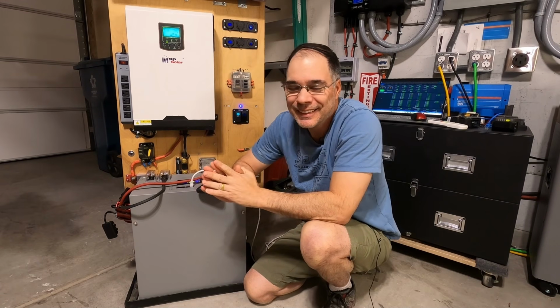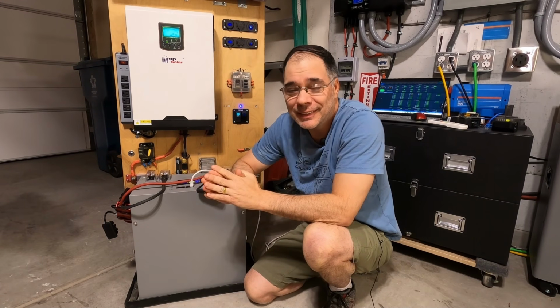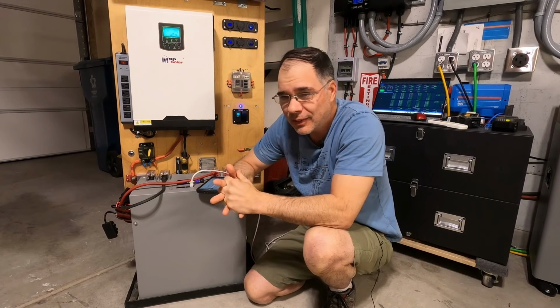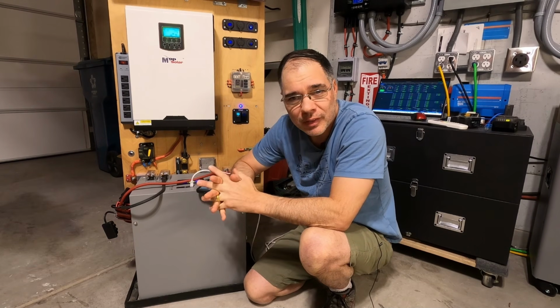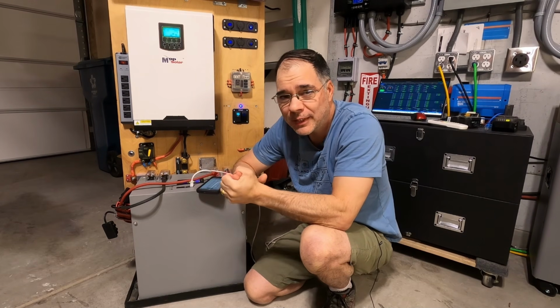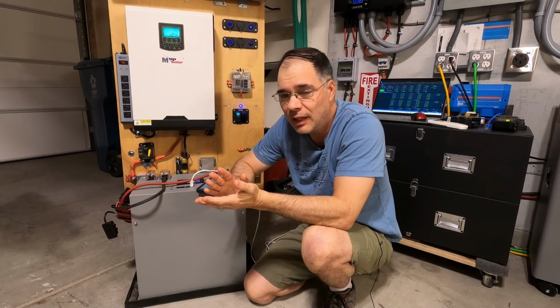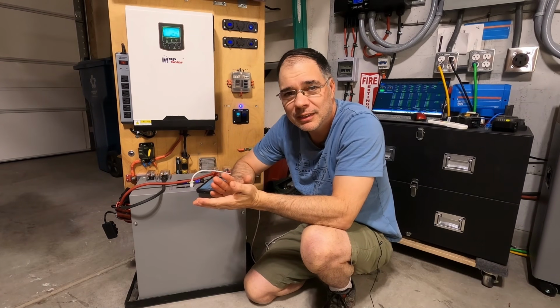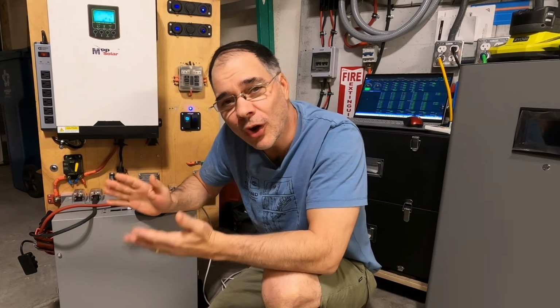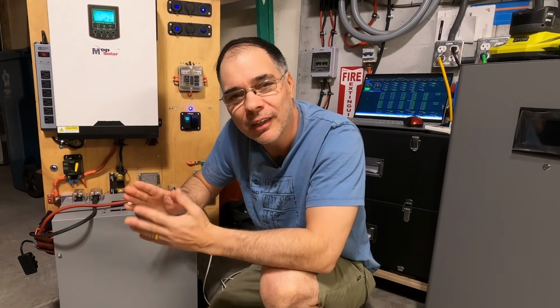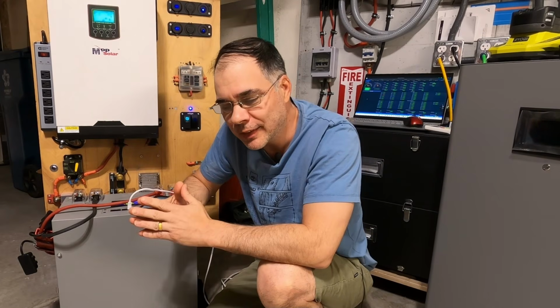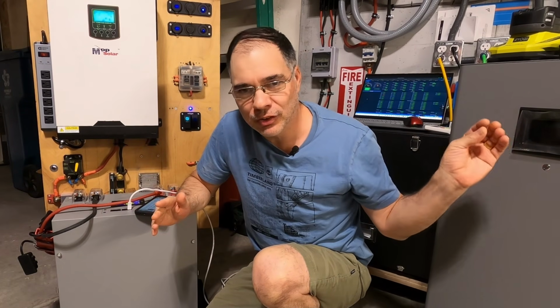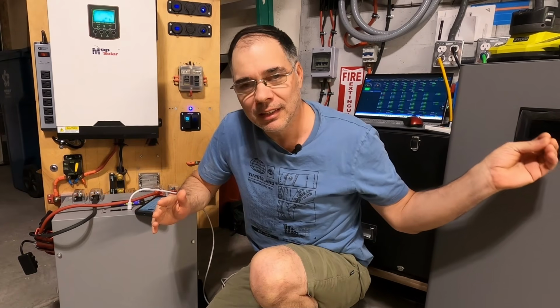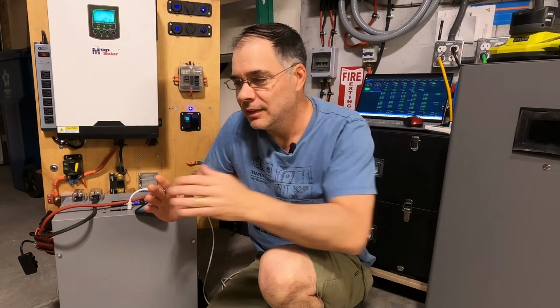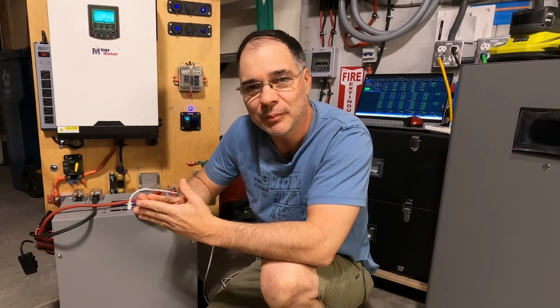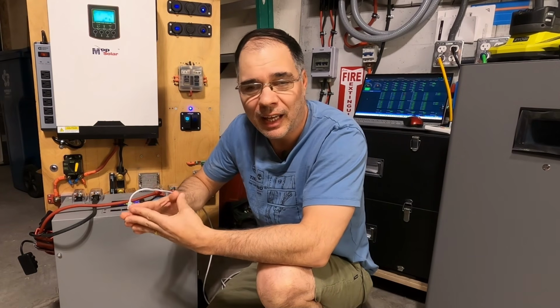Alright, so that's pretty much where the likes stop. This box has some issues, to say the least. So starting with the cells, they're a bit difficult to install with the fact that there's no removable pressure plate. So I would definitely like to see a removable pressure plate in this box in the future. No DC rated external breaker. You know, Yixiang really set a precedent with their vertical box having the internal fuse and the DC rated breaker on the outside. With that allows you to disconnect the battery from your system for maintenance and gives you that extra layer of protection.